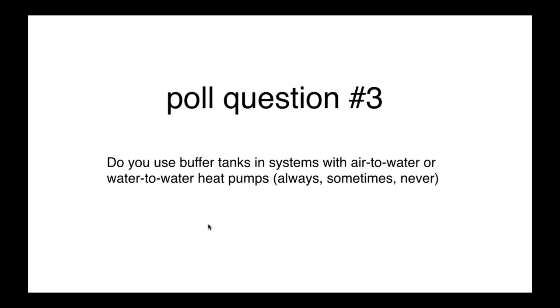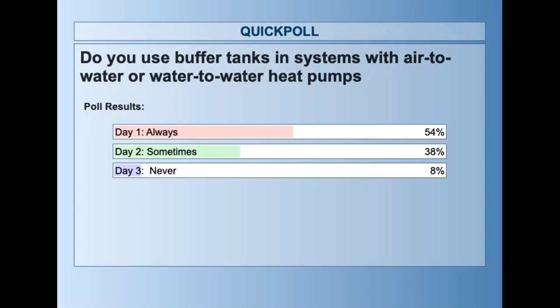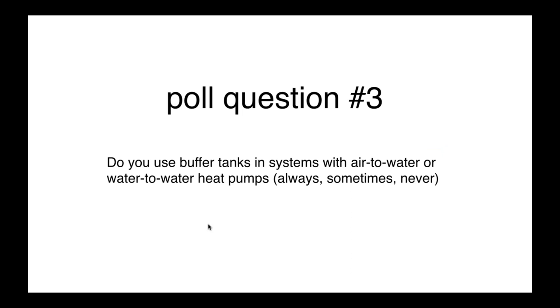That looks like always is going to win by quite a bit. 54% for always, 38 for sometimes, 8 for never. Yeah. And I should point out, you might say the people that are never doing it are headed for problems. Well, heat pump technology, as we get into inverter compressors, as long as you are creating a distribution system that doesn't have a load smaller than the minimum capacity in either heating or cooling of the heat pump, yeah, you can do it without a buffer tank.